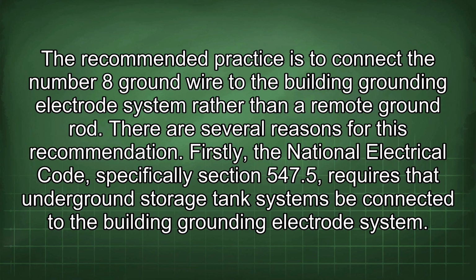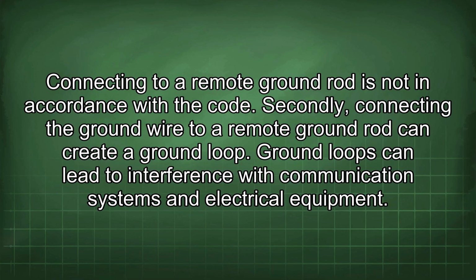Firstly, the National Electrical Code, specifically Section 547.5, requires that underground storage tank systems be connected to the building grounding electrode system. Connecting to a remote ground rod is not in accordance with the code. Secondly, connecting the ground wire to a remote ground rod can create a ground loop. Ground loops can lead to interference with communication systems and electrical equipment.